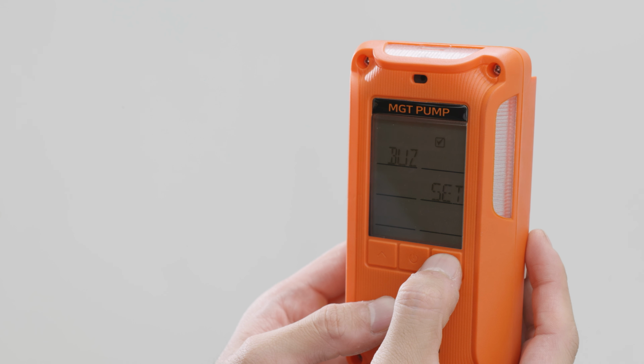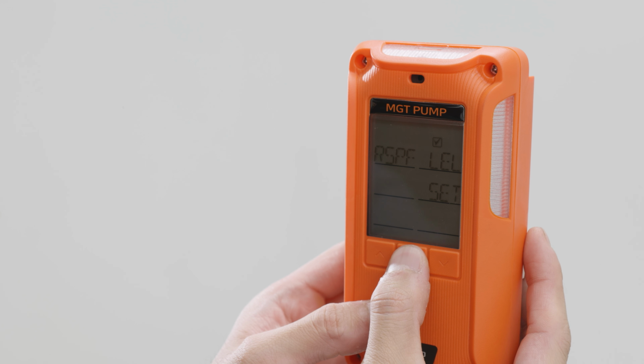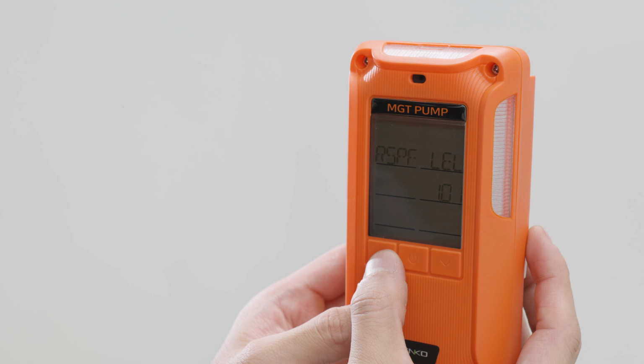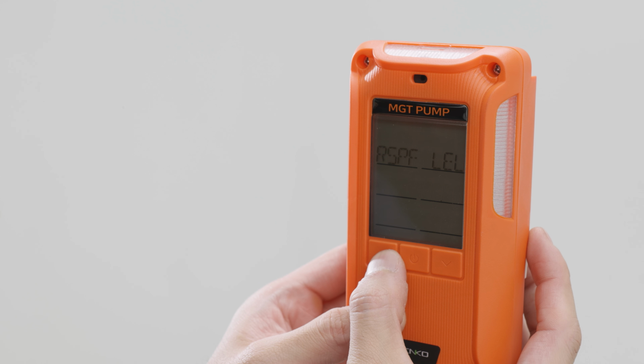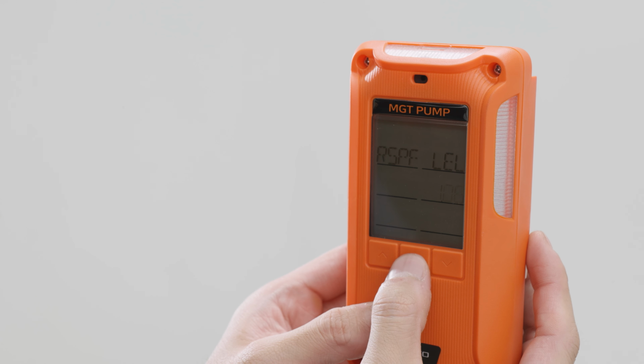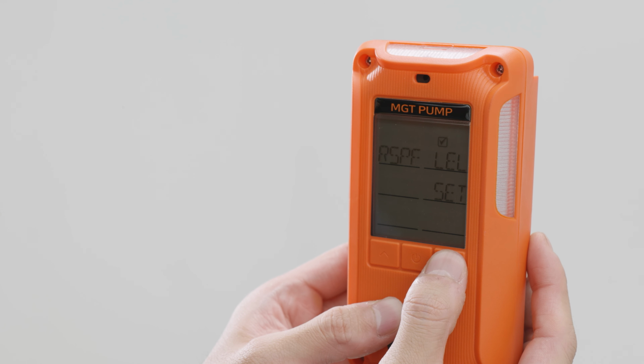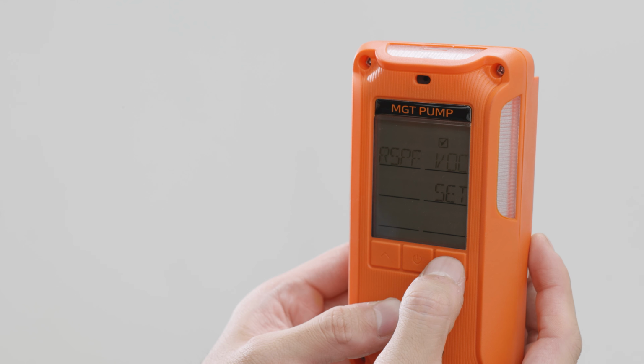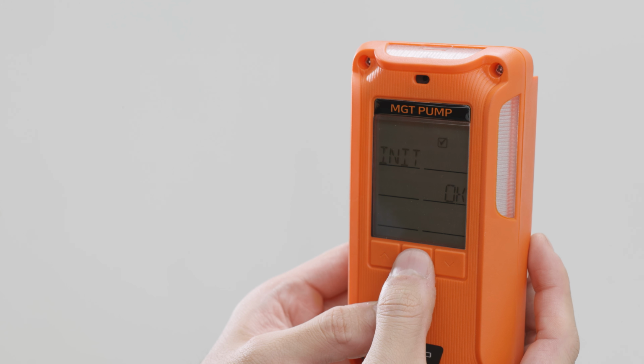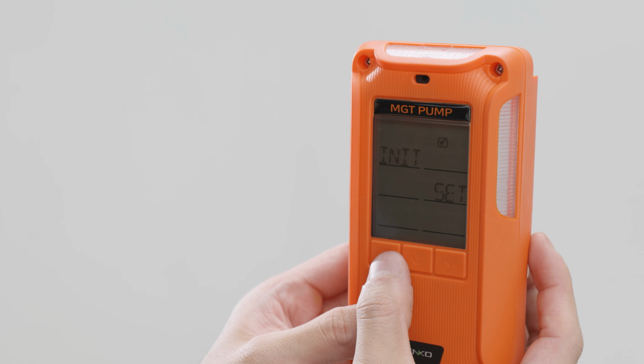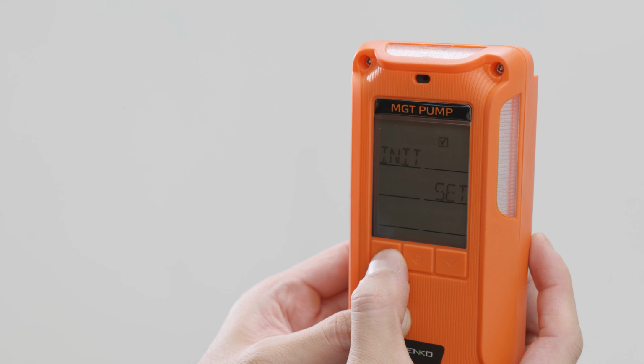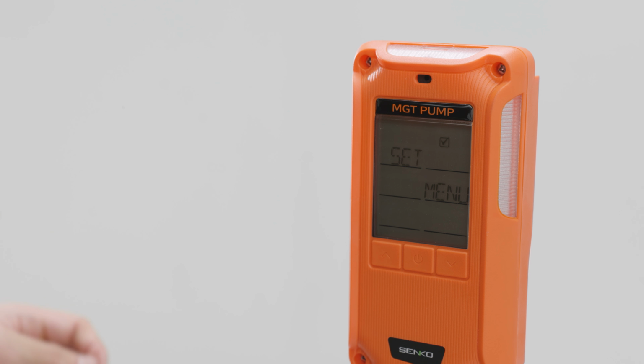Before explaining the RSPF LEL and RSPF VOC settings, it is important to understand that LEL and VOC include a very wide range of gas types. Each sensor responds differently depending on the gas type. For example, suppose there is a situation where you want to specifically detect gas B and the response factor RSPF of gas B for the LEL or VOC sensor used in the SP-MGTP is 2. In this case, by entering the RSPF LEL or RSPF VOC menu and changing the default value from 1 to 2, the device will be optimized to detect the specific target gas, gas B.